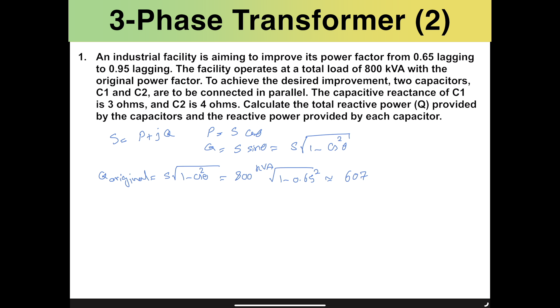So Q for the original case is S times the square root of 1 minus cos theta squared. Here S is 800 kilovolt amperes, so Q equals 800 times square root of 1 minus 0.65 squared, which turns out to be around 607 kVAR, since this is reactive power.